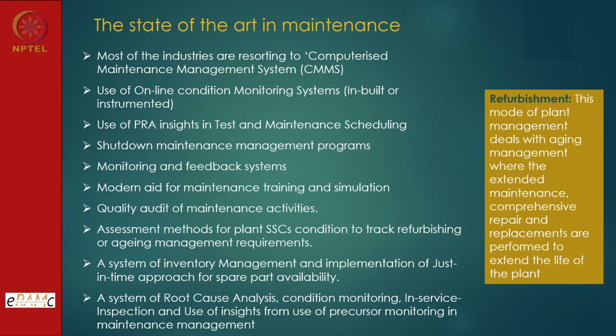Online condition monitoring has also become part of the state of the art. There are some critical equipment where redundancy cannot be provided due to constraints, so failure of the equipment affects plant availability. For such cases, whether it's a bearing, we do continuous monitoring of oil level, temperature, and vibration. This becomes condition-based maintenance.